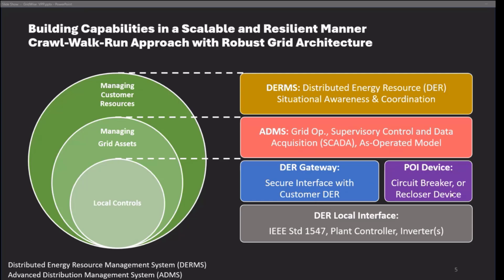We're also leveraging the point of interconnection device not just as a protection, but also a fail-safe device, so that if the schedule is violated, the local controls can disconnect the DER and prevent grid impacts.